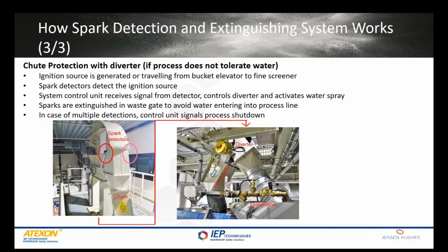During the alarm, when a spark is detected, the spark detection system controls the diverter and guides the material flow and ignition sources to the waste gate. This way we don't need to spray water into the fine screener, which could lead to a mess or even porridge, because the powder is now grain dust. After 5 seconds, the spark detection system deactivates the water spray and the diverter returns to normal mode. And the pressure booster station, which contains a water pump and tanks, is similar to dust pipe protection.